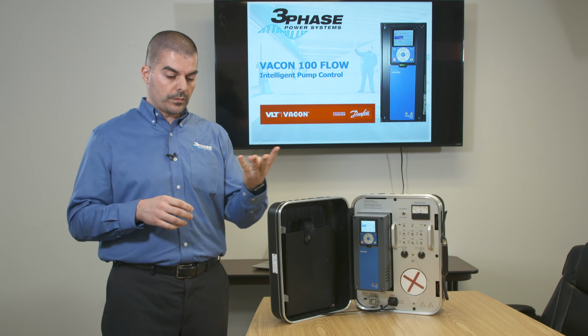Most drive applications require many external components in order for them to work, such as line reactors, EMI, RFI filters, manuals to operate and to troubleshoot and to program, things like RTD relays or thermistor relays, communication protocols such as Ethernet, Modbus, TCP, and so on and so forth. Everything actually has been embedded in this drive. We have communication on board, the most modern and fast communication, Ethernet, Modbus TCP/IP, Profinet IP, and others directly built into the drive. And this simplifies things. Before we had so many components outside of the drive, now everything is inside. So this makes it much, much easier and simpler for clients to operate and use the drives.